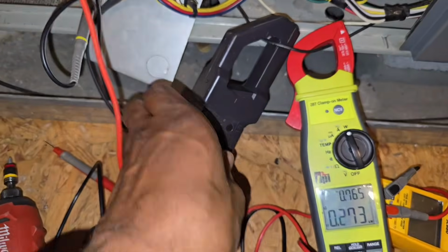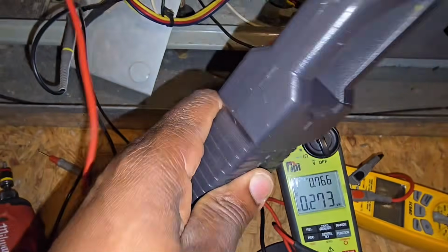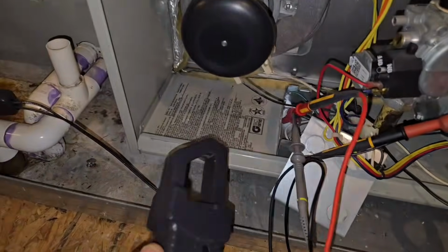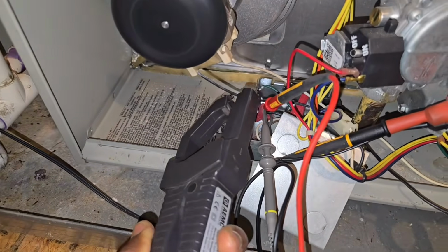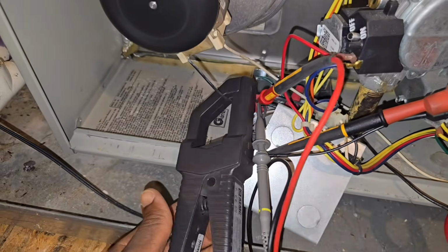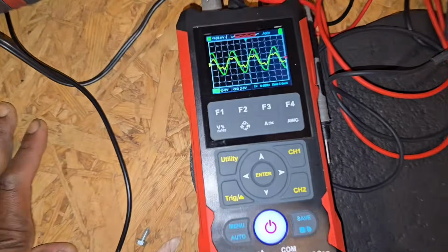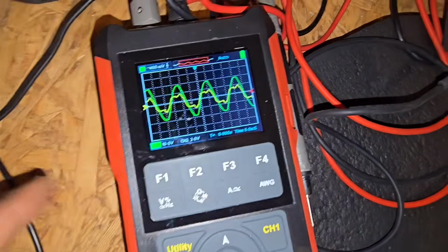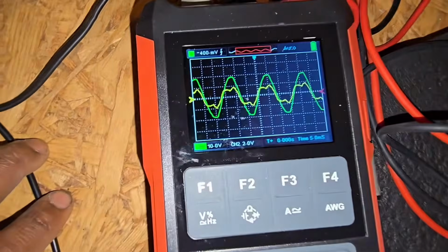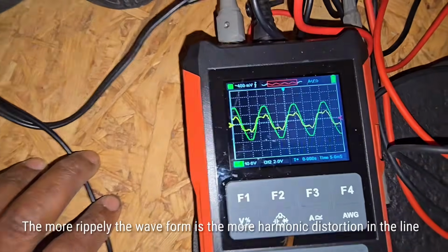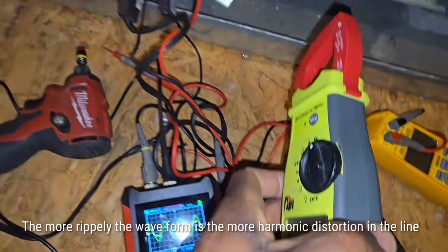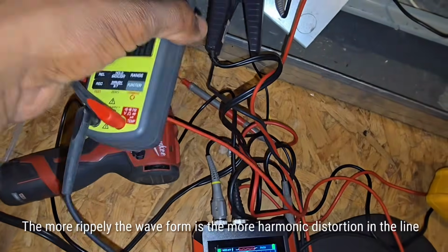I'm going to take the current for the inducer motor. Okay, so that's what the current for the inducer motor looks like. You can see it's much more ripply current, and we can check our power factor for that as well.